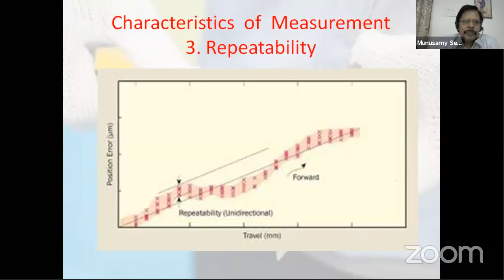The repeatability should be available in your measurements wherever, whenever you take them. Then hysteresis: as you change your measurements from positive to negative, the variation must be, strictly speaking, a straight line from left to right, which is not going to happen in any instrument. So what is the variation? That is your starting value itself.